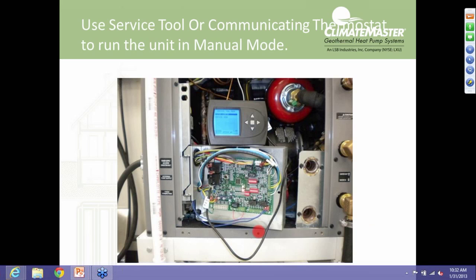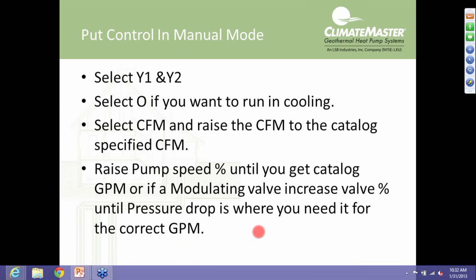All right, so we're going to go into manual operation as I've kind of mentioned before. We're going to start from the bottom up here. And again, the first thing we're going to do to reiterate is we're going to run that pump speed up. So we're going to see GPM between 50 and 90%. So what I'd recommend maybe starting about 65%, go back into control diagnostics, see what your flow rate is, and then start adjusting the percentage from there, kind of get a start point. And then, you know, it might take 2 or 3 times to get to the flow rate that you're looking for, like on that 3-ton heat pump, 9 gallons per minute.